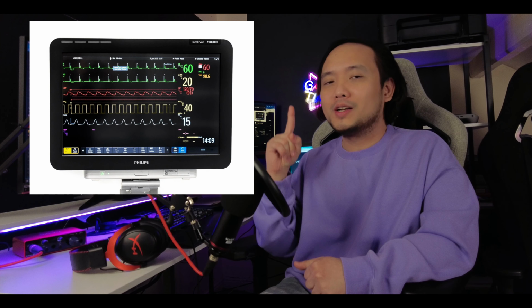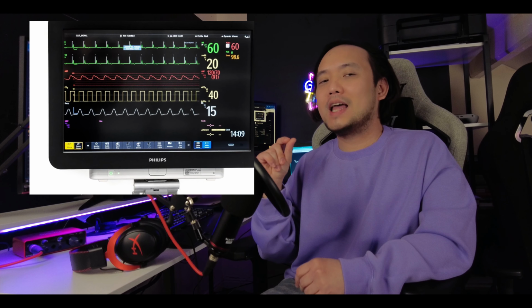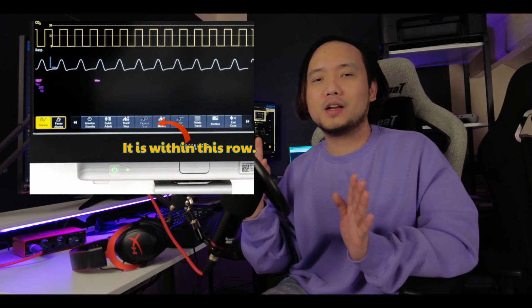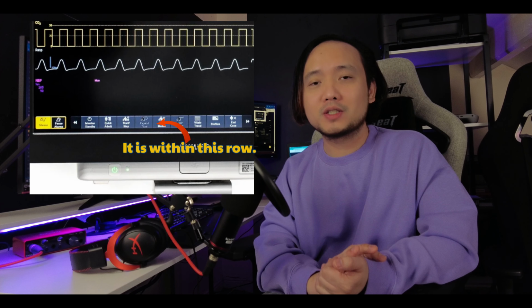We're going to look for the zero. Once we click that, the monitor will calculate and remove any atmospheric interference that may cause an inaccurate blood pressure reading. And we do that once or twice per shift. Next would be the square test.